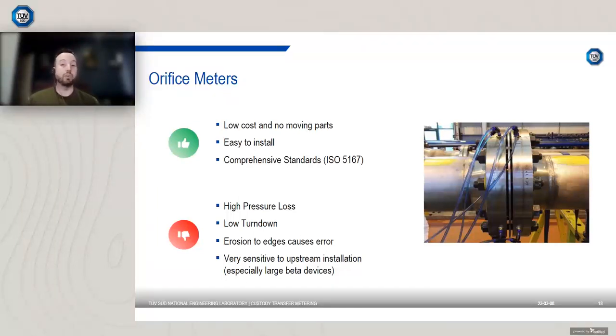So that needs to be considered. They've got a relatively low turn down. So typically 3:1 to 5:1 is the turn down you can expect. You can increase the turn down by utilizing more than one differential pressure measurement device. Typically the limitation is the range of differential pressures you can measure. But if you have a bank of differential pressure transmitters that measure a low, medium and high range, you can increase the turn down maybe up to 10:1.